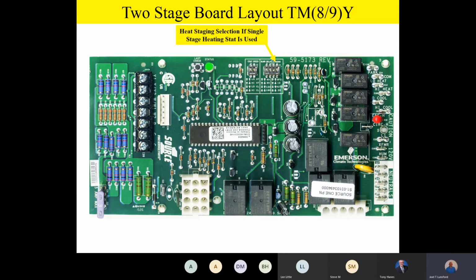If you're not going to use that staging function, if you're stuck with a single stage thermostat, put it someplace other than off. Even if it's 10 minutes or 20 minutes, auto is recommended. The only time those switches should be in the off position is if you have a 2-stage thermostat where you can actually control W/W1 first stage heat and then W2 second stage heat. Any questions or comments on those staging dip switches and the cool feature that I've just described to you?